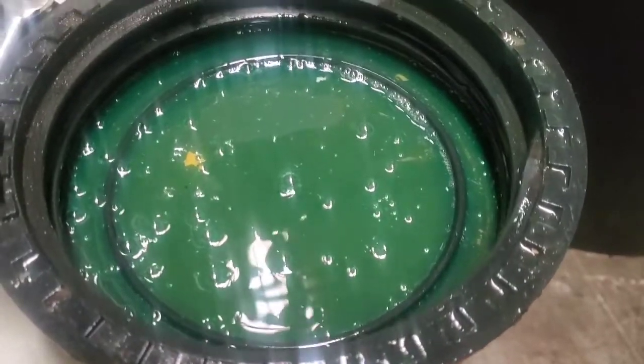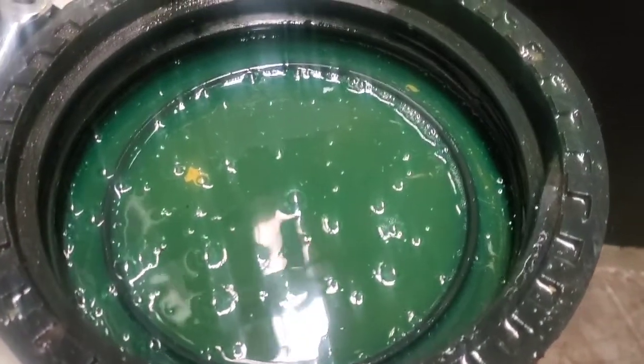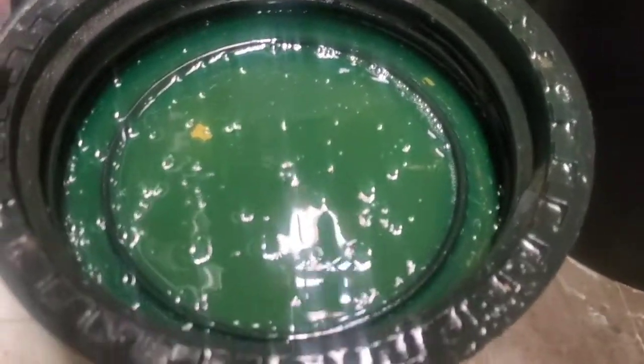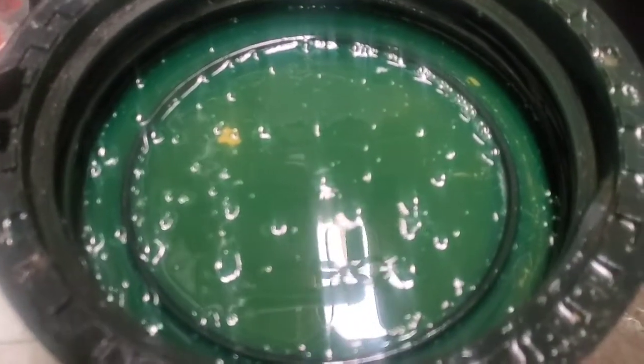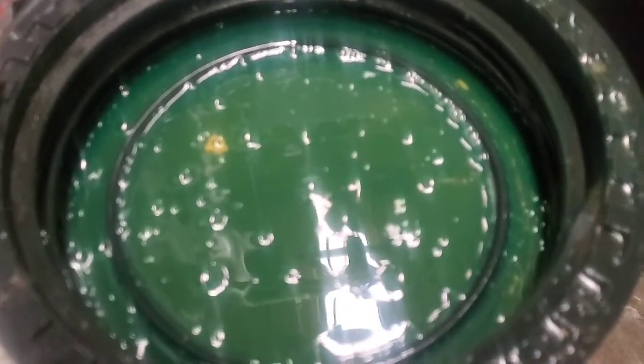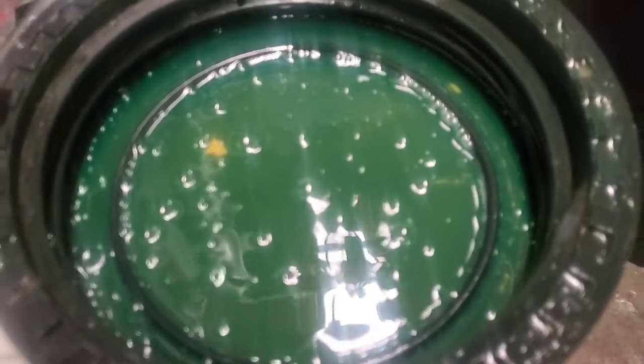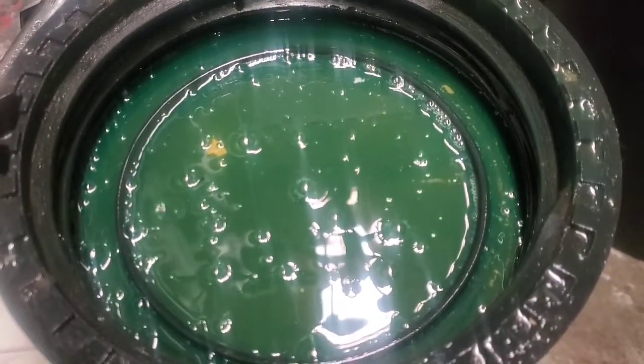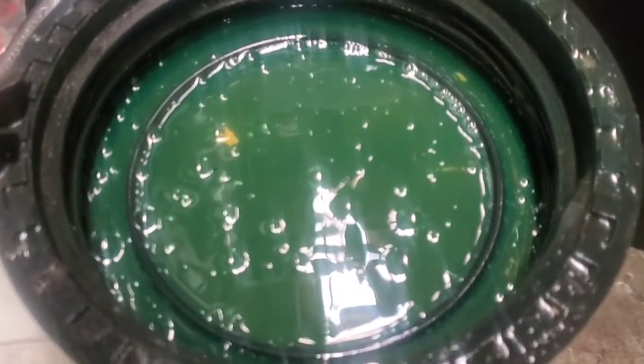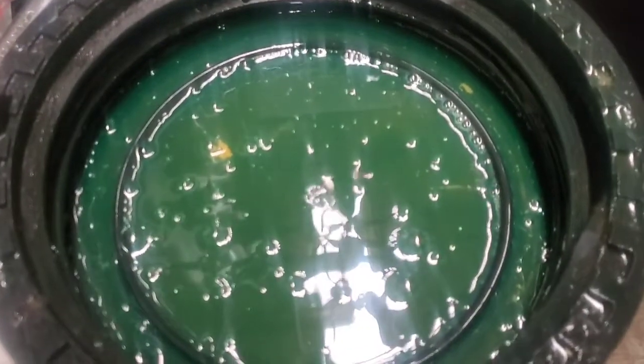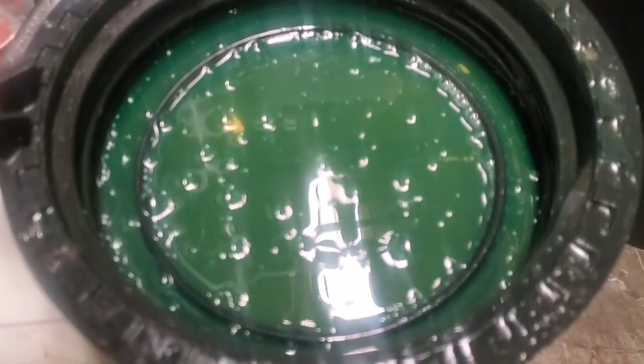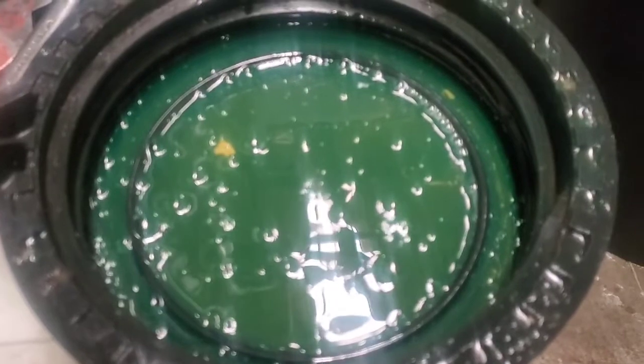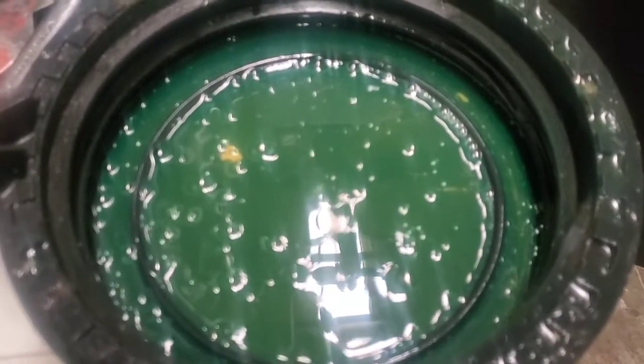Alright, so as you can see, we ended up losing a lot of oil from this system. Oh, and the reason why it's green is because a few years ago we had to put some dye in the system. And I think my technician put a little bit too much dye in the system to find that leak. So, anyway, the point is we're going to have to replace some of this oil so that our system doesn't run low on oil.